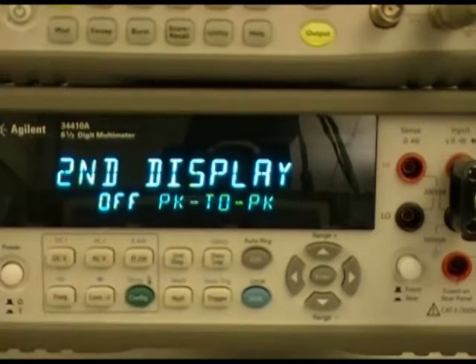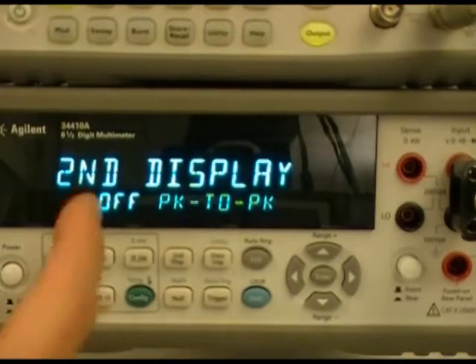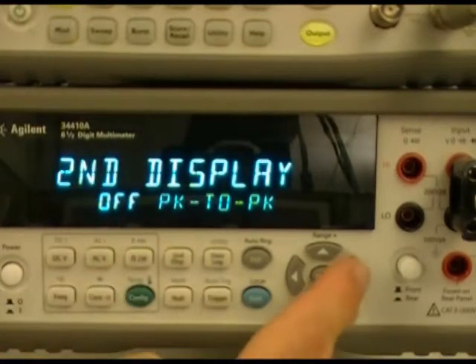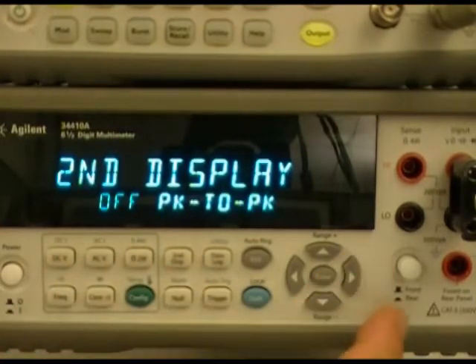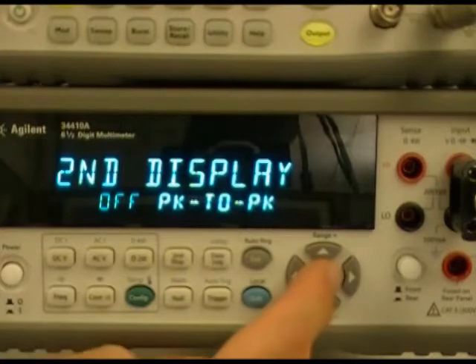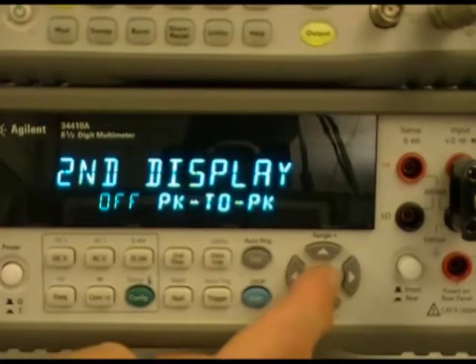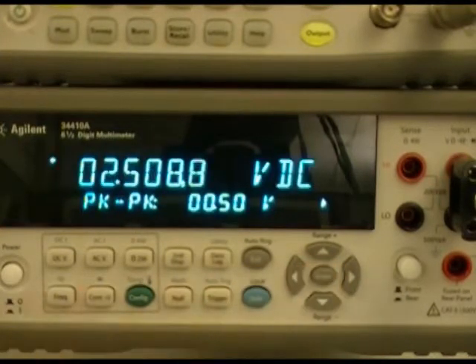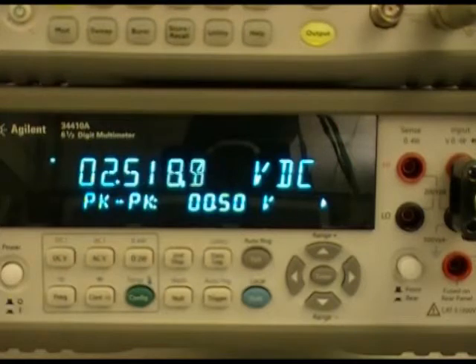You can see we have a choice of turning it off or for DC volts looking at the peak to peak value. So I'm going to choose the peak to peak value and hit enter.